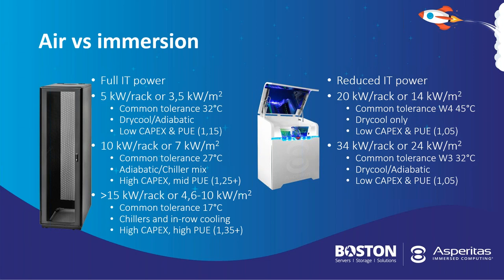Normally, commonly, you could potentially cool that with 32 degree Celsius air temperature, which means you can make a very efficient data center environment with dry coolers and adiabatic cooling. This is what the larger scale data centers and highly efficient data centers are doing, with low capex and low PUEs of about 1.15.